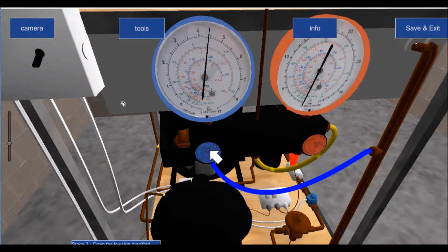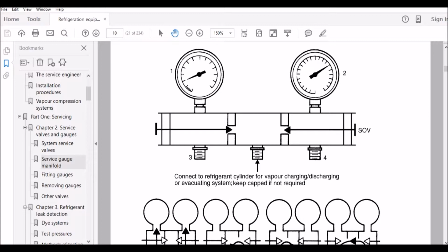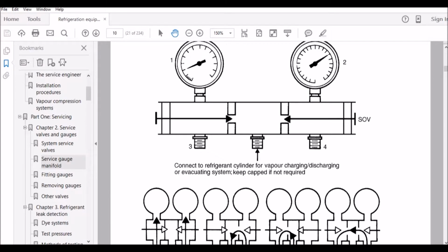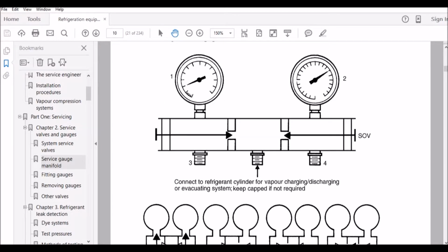Anyway, so I open this here, and you can see once I open this, refrigerant will now enter in here. So what does that mean effectively? That means that as soon as I open this shut-off valve, the refrigerant that's in this area here, that's feeding pressure or giving my gauge pressure, enters into the service area. So now my yellow hose line is full of refrigerant, but thankfully we have it blanked off. My actual valve manifold has got refrigerant in it as well. So in other words, the refrigerant has now gone from my blue side gauge area into my manifold area and hasn't gone any further for the moment.